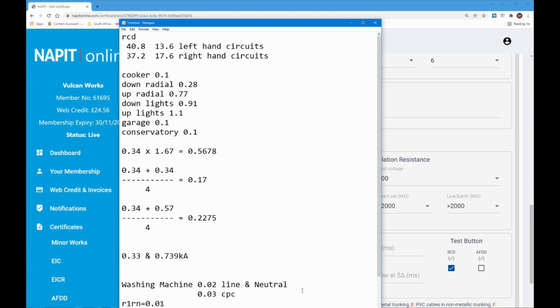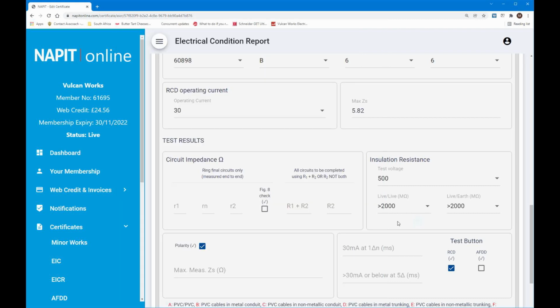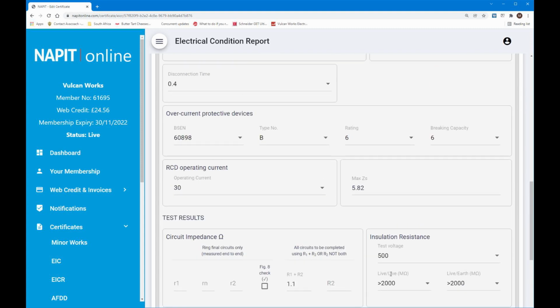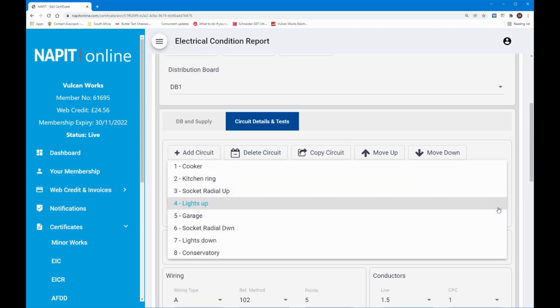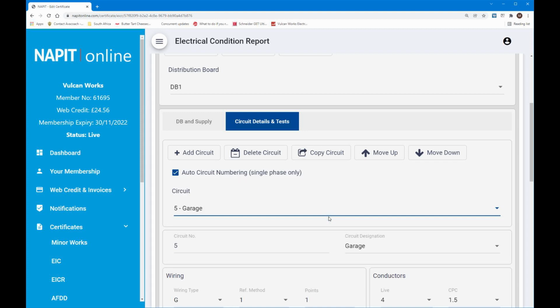And the R1 R2 for the upstairs lighting circuit was 1.1. Add that to the 0.33 and we get 1.43, which is absolutely fine. I was able to do the insulation resistance test on the lighting circuits upstairs because there was no LED stuff, so it was absolutely fine to do that. I just took all the bulbs out, so that's fine. That came out at 500. And again, same readings for the RCD. Okay, that's all done. Okay, so that's all the circuits on that RCD. Like I said, we'll come back to that ring last. So move on to the garage circuit.